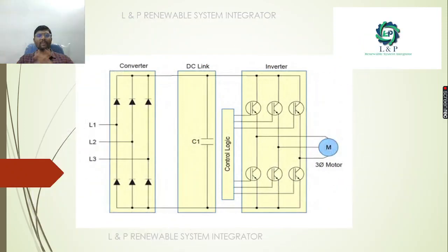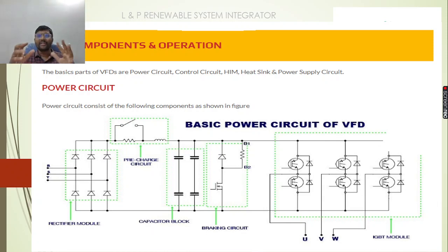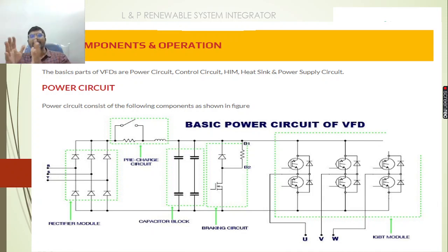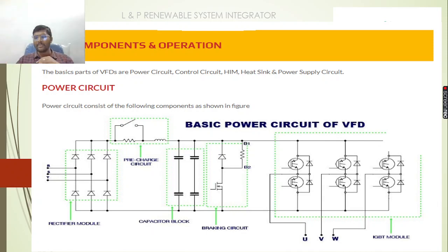When we look into the variable frequency drive, it will have a converter, a DC link, and an inverter. Getting deeper into the variable frequency drive, it has some most important components: a power circuit, a control circuit, a heat sink, and a power supply circuit. Going more in-depth, we have a rectifier module, a pre-charge circuit, a capacitor block, a braking circuit, and finally an IGBT module.